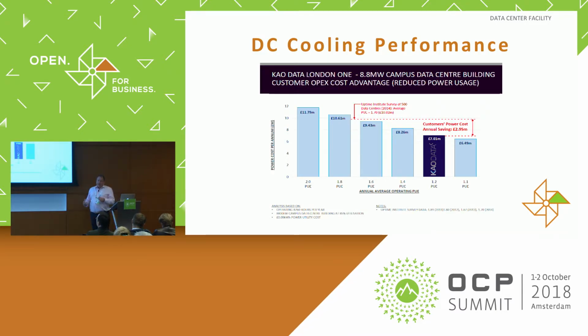In terms of what that means to customers, and maybe some of these figures are a little out of date, the latest Uptime Institute global survey showed that the average PUE is about 1.58. So we're a little bit out here, but you can gauge from here what the savings could be. If you go back to 2014, the numbers there were about 1.7 as a global PUE. If you compare that to what we're operating at, 1.2, you can actually save on an 8.8 megawatt building about £3 million a year in terms of energy saving. And that's quite impactful really in terms of the overall operating costs.